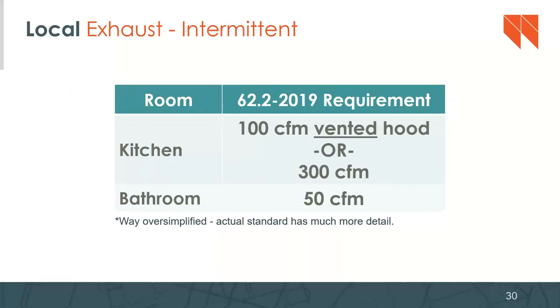So to comply with 62.2, the design needs to accommodate that, right? You've got to have a duct and a fan that are capable of exhausting, in theory, 50 CFM. So you just want to make sure the static pressures that the design was done under are achievable with what gets installed, i.e., the duct is sufficiently large. Usually for a bathroom, that's a 6-inch or 4-inch round sheet metal duct, and then a fan that is able to push that air through that duct at the distance that it needs to go.